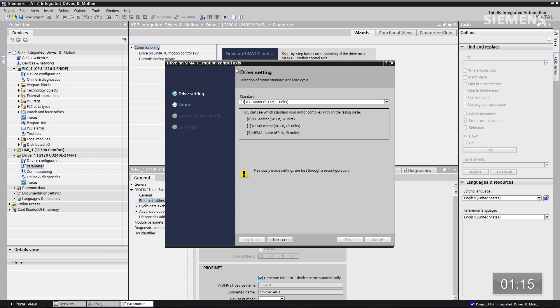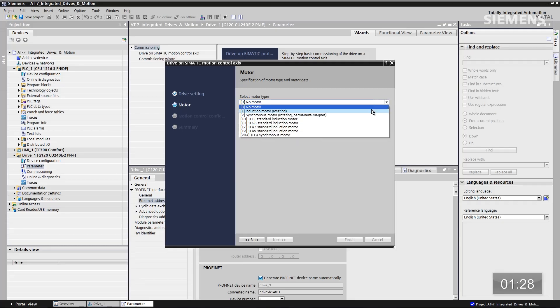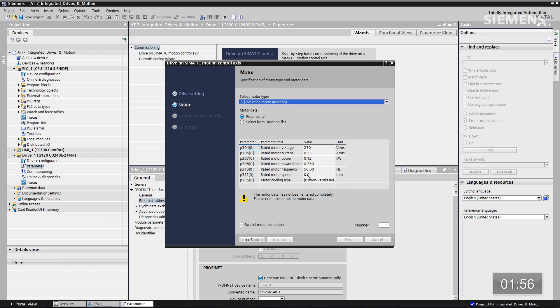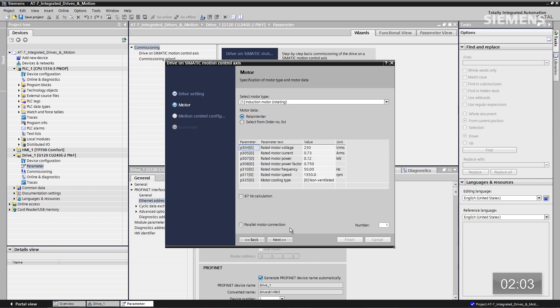Now we have a dialog box that pulls up and we can start inputting our data for this particular parameterization. First choice is 50 or 60 hertz — it is 50. Now I have the option of choosing the type of motor: it's going to be an induction motor. Now I can input my nameplate data: voltage is 230 volts, amperage is 0.73, kilowatts is 0.12, power factor is 0.750, frequency is 50 hertz, and RPM is 1350. So now I've got my nameplate data.